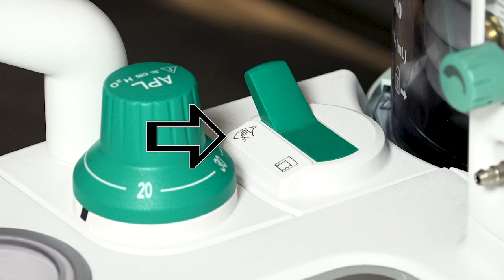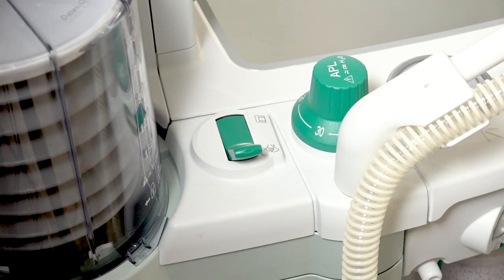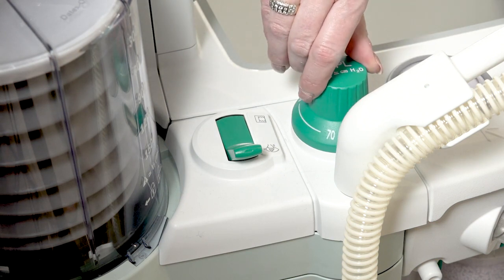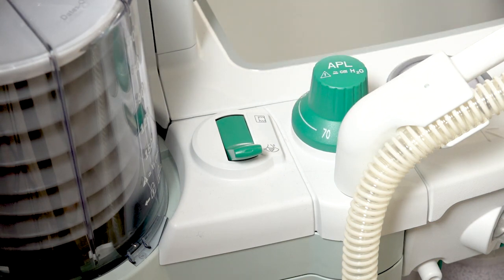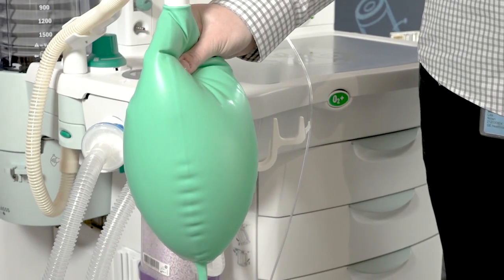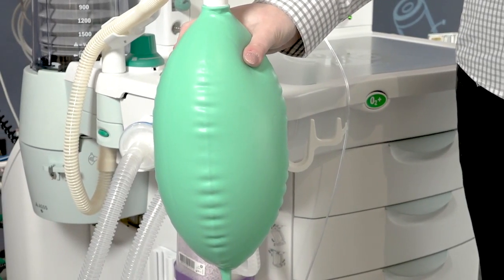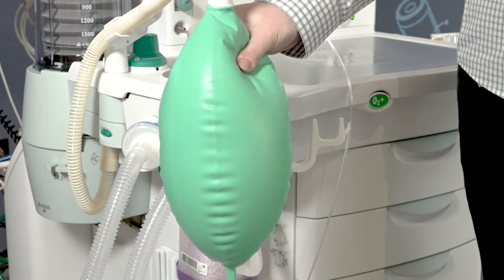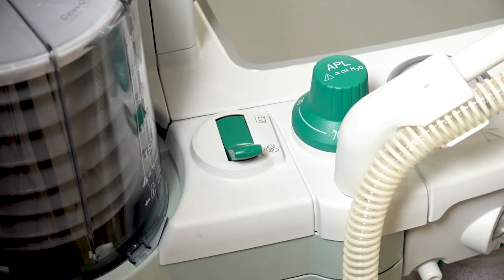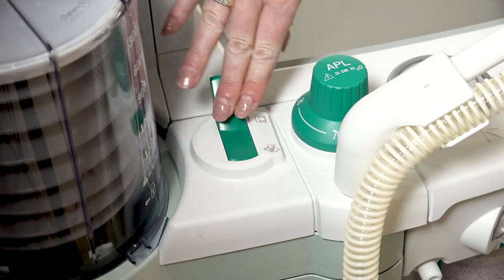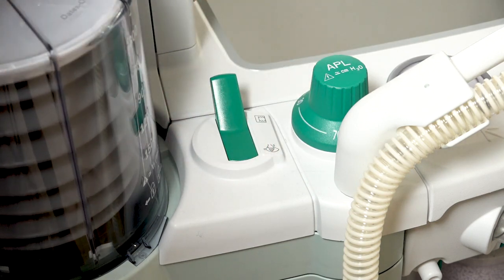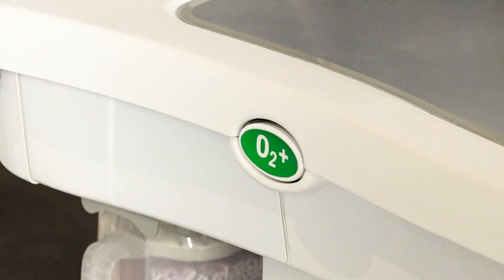When the device is in bag mode, the device is not providing any ventilation support to the patient. When the device is in manual ventilation, maximum pressure is managed by the adjustable pressure limit, or APL valve. If ventilating the patient manually, ensure the APL pressure limit is appropriate for the patient. Mechanical ventilation begins by moving the bag to vent switch to the vent position. Ventilation will begin at the previous configured or default settings. If needed, press the O2 flush button to inflate the bellows.